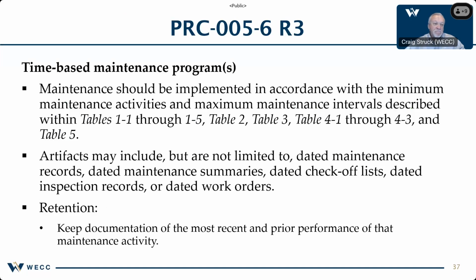Thank you. Okay, so rolling into R3, R3 utilizes time-based maintenance. Time-based maintenance is most commonly used amongst most entities, and this maintenance is implemented in line with the interval tables described within the standard. So artifacts include, but aren't limited to, dated maintenance records, maintenance summaries, checkoff lists, inspection records, or work orders. So make sure to keep the documentation of the most recent and prior performance of the maintenance activity that you perform. Next slide, please.